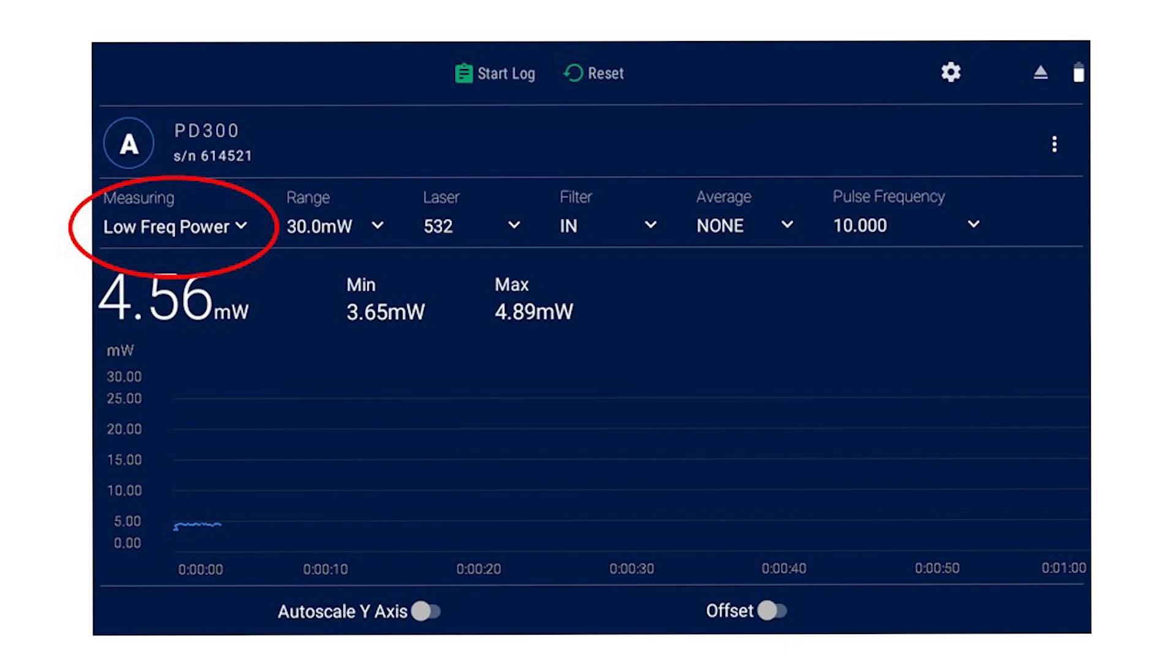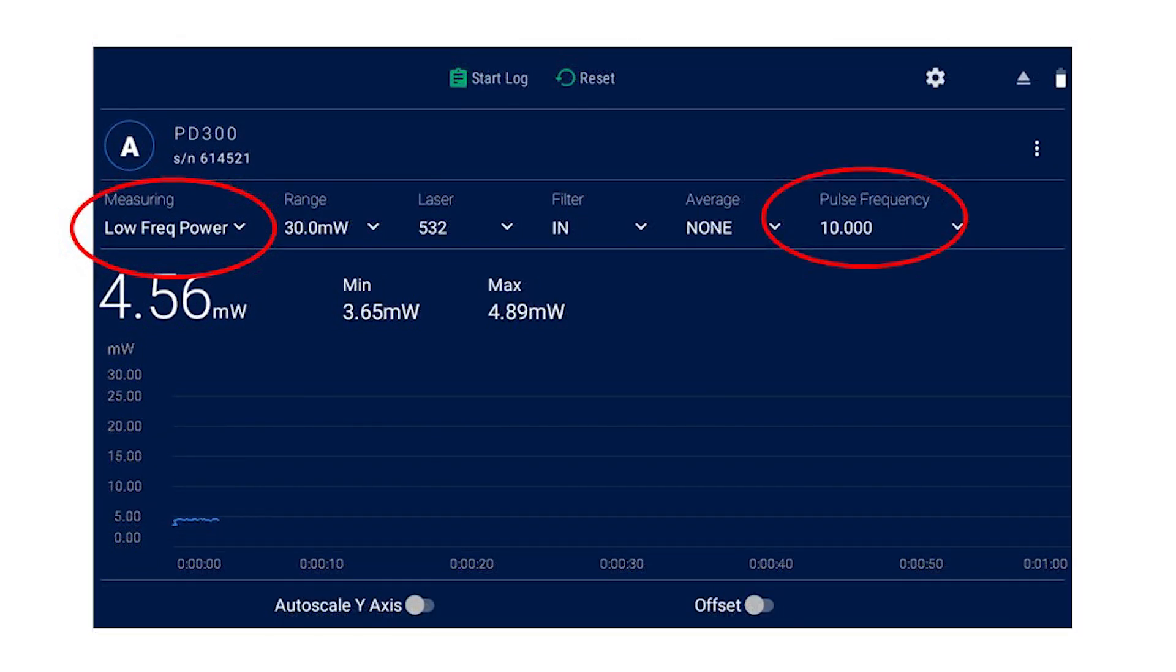The sampling rate is internally adjusted to match the actual pulse frequency, which the user is prompted to enter. No more beat frequency. The gain is lowered and the resolution is increased so that we get accurate measurements of the low average power without being thrown off by saturation caused by the high peak power.